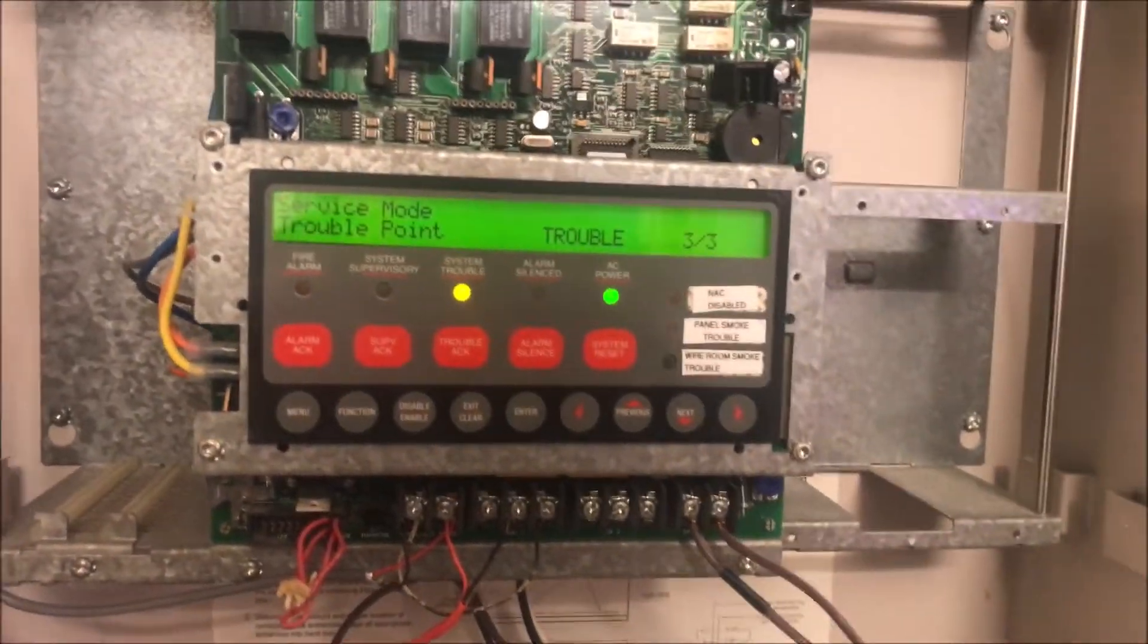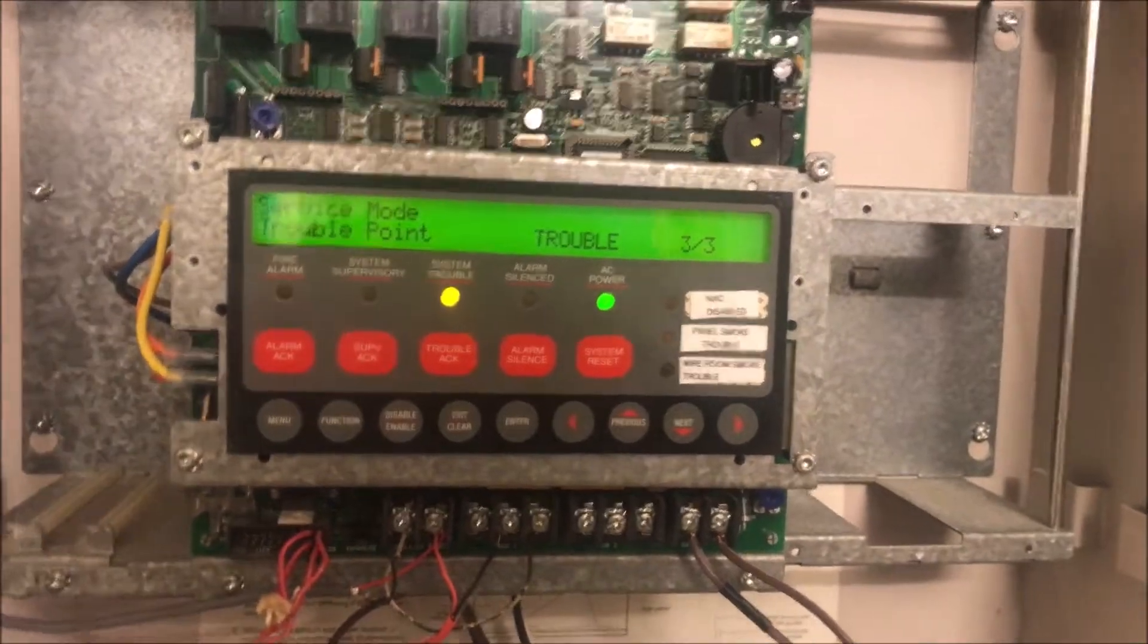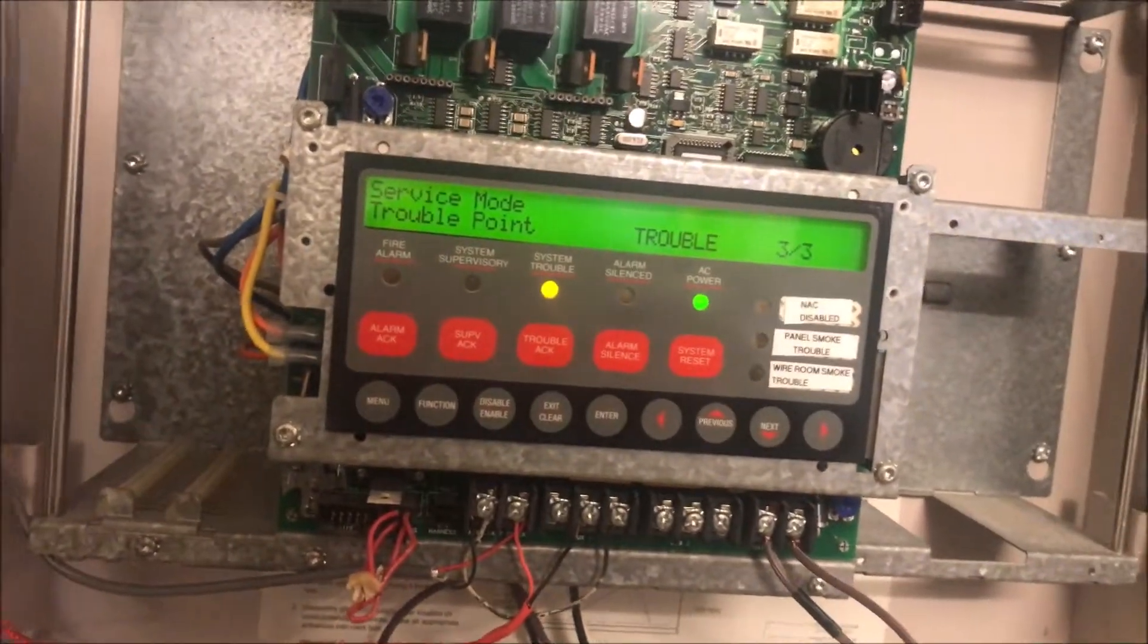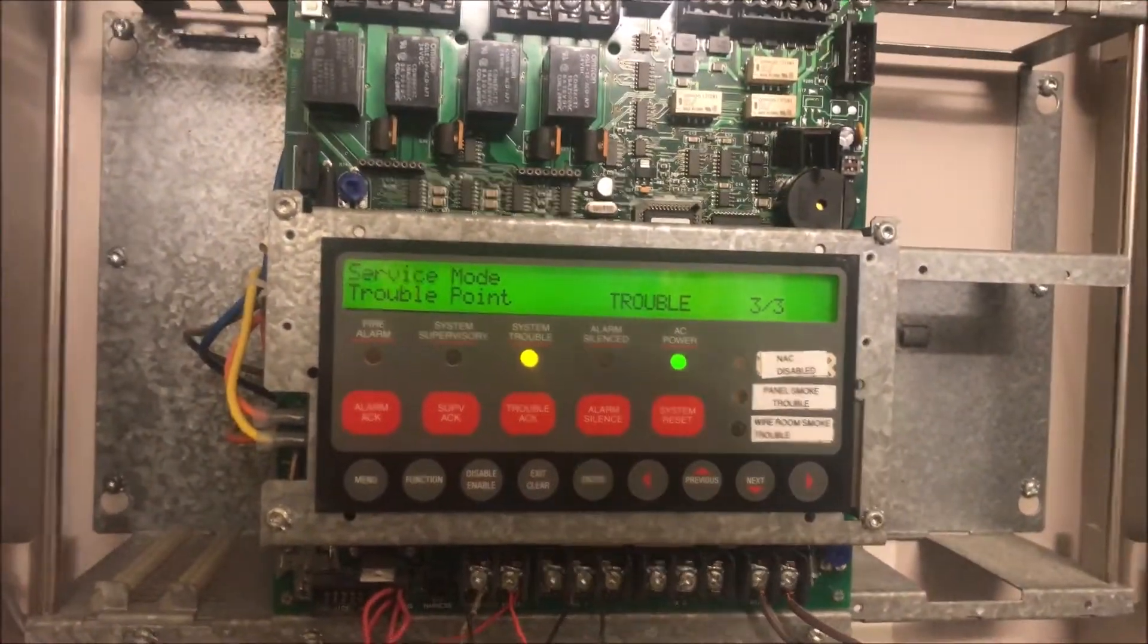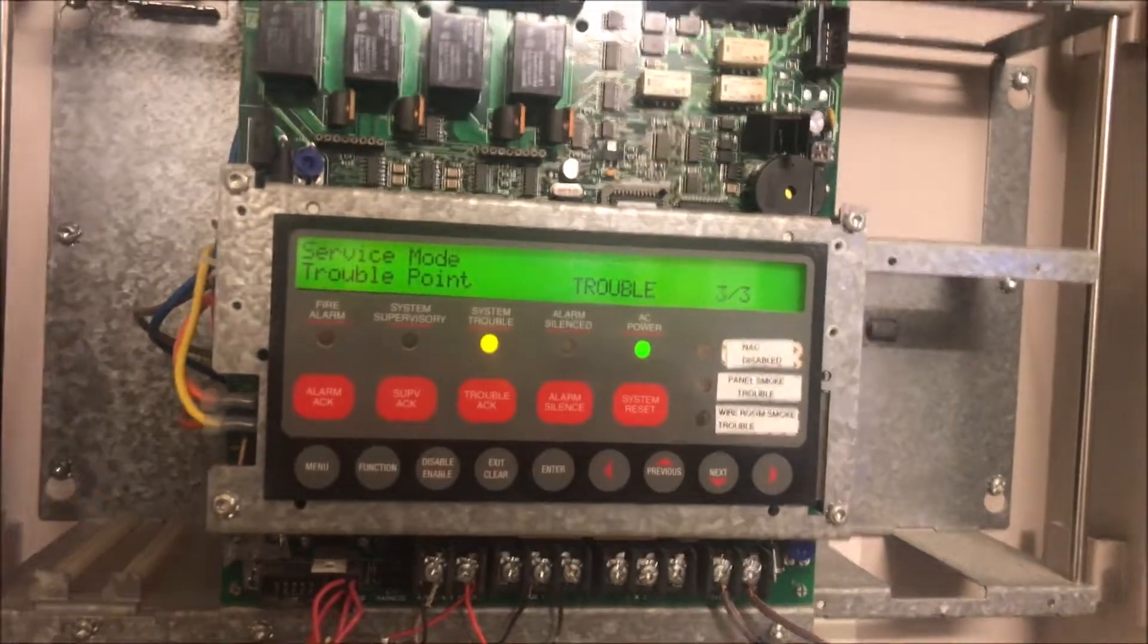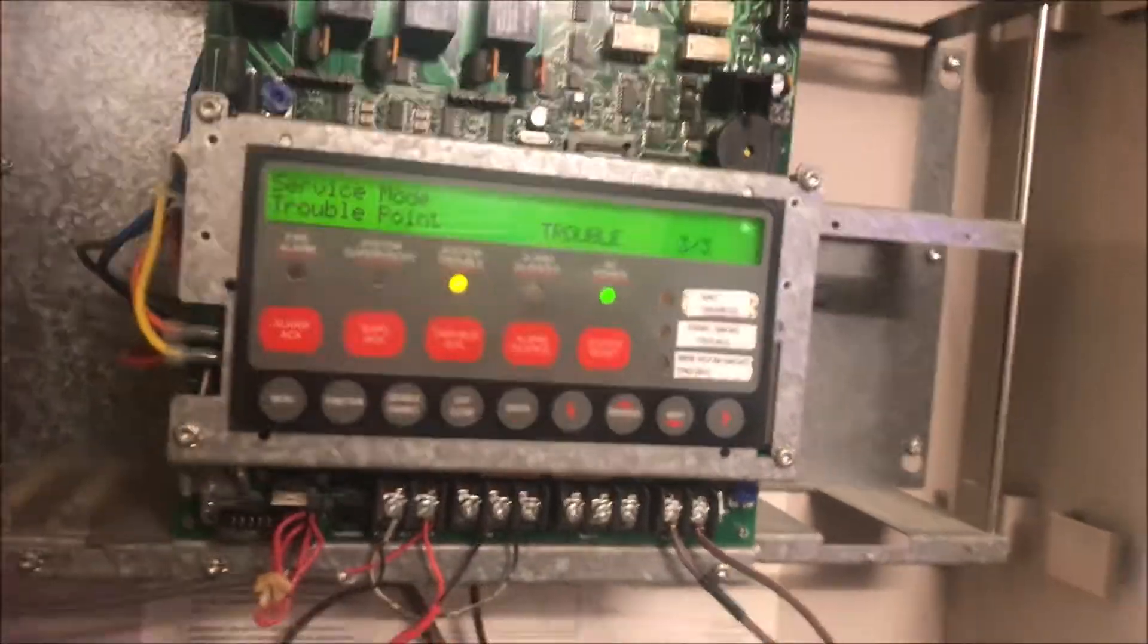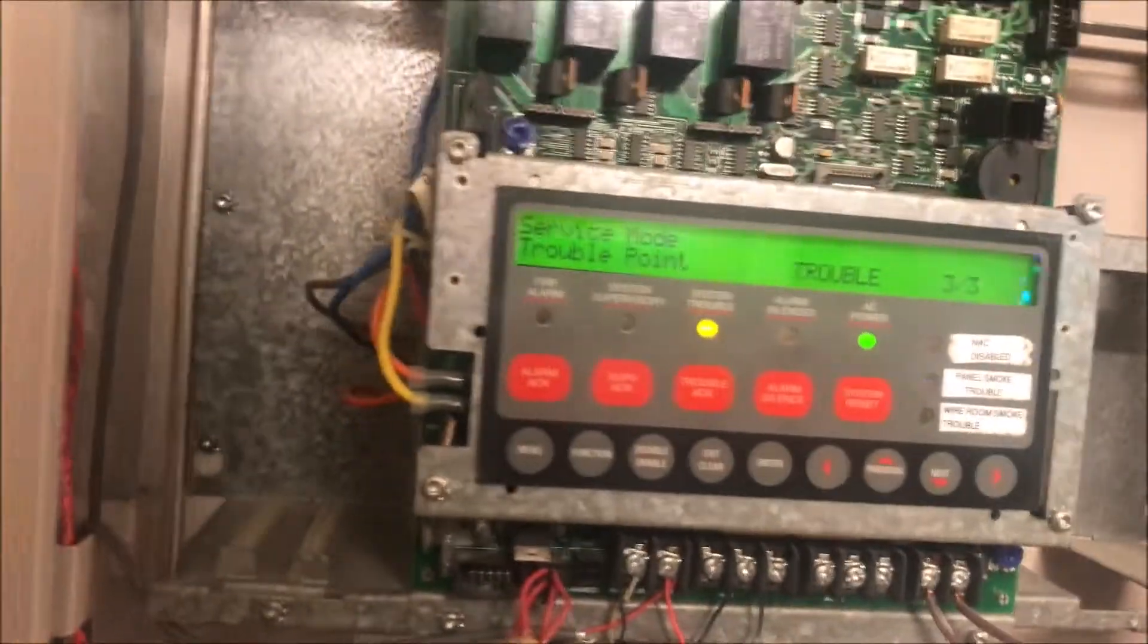We will get a service trouble that will not go away until the panel is either cold or warm restarted. The only way to clear this trouble is to restart the panel, but we're going to be doing that anyways because we are going to be adding a new point.